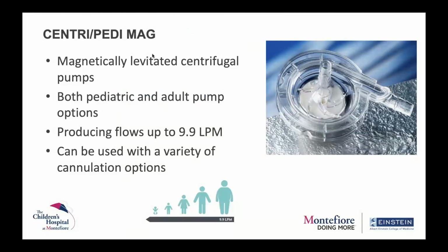So this is a continuous flow pump. As you can see here in the picture, it is a rotor that is magnetically levitated. There are two magnets sitting on top of each other and rotating, and this rotor sits outside the heart. It can be used for both pediatrics and adults, depending on the size of the cannula. It can provide flows up to almost 10 liters. And depending on the size of the cannula, you can put it in a baby as well as all the way into a huge adult.